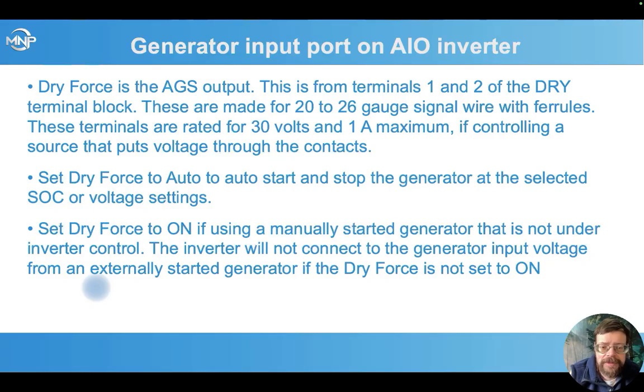You'll want to set your dry force contact to auto if you want to auto start and stop the generator at the programmed state of charge. If you're using a manually started generator that's not under the control of the inverter, you're just starting it yourself, or you're using some other type of control to control it, then you need to set the dry force to on. This isn't actually controlling the generator, but it's telling the inverter, look for AC power coming in on the generator input. So that's something that throws a lot of people off, is that when you're using a manually started generator, you have to set the dry force to on to let the inverter know to look for a generator.